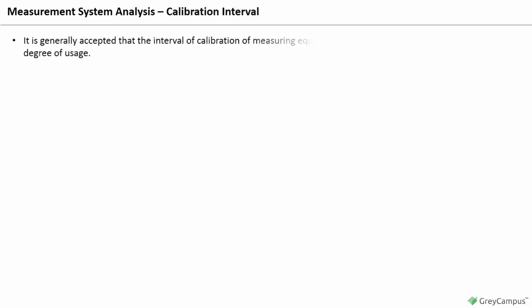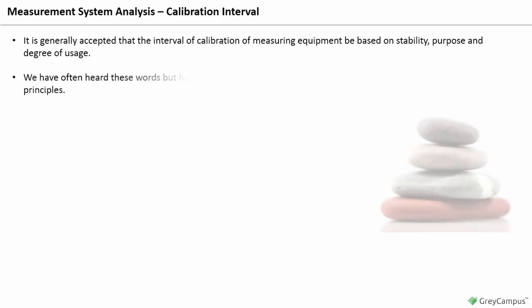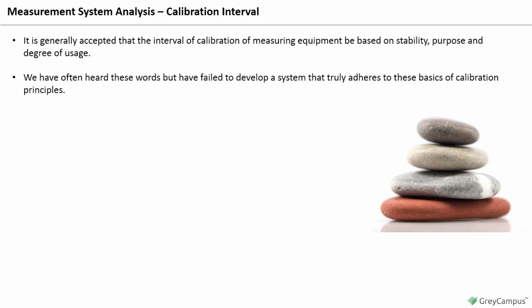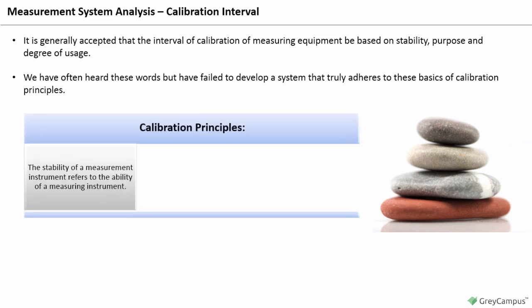Calibration interval. It is generally accepted that the interval of calibration of measuring equipment be based on stability, purpose, and degree of usage. We have often heard these words but have failed to develop a system that truly adheres to these most basic of calibration principles. The stability of a measurement instrument refers to the ability of a measuring instrument to consistently maintain its metrological characteristics over time. This could be determined by developing records of calibration that would record the as-found condition as well as the frequency, inspection authority, and the instrument identification code.